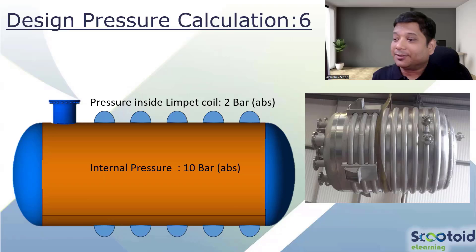The answer for this may surprise you. External pressure - now just wait for some time, let us have a discussion. External pressure for which you will be designing, considering you have a vacuum also which may be there, external pressure will be only one bar absolute.